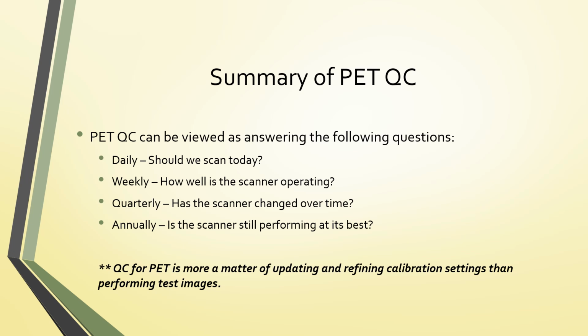For weekly QC, we want to know, how well is the scanner operating? Have there been any significant changes through the week or over the weekend that would change its ability to operate efficiently or effectively? For quarterly QC, you want to know, has the scanner changed over time? You're looking at the overall stability of the system. And annually, you want to know, is the scanner still performing at its best?